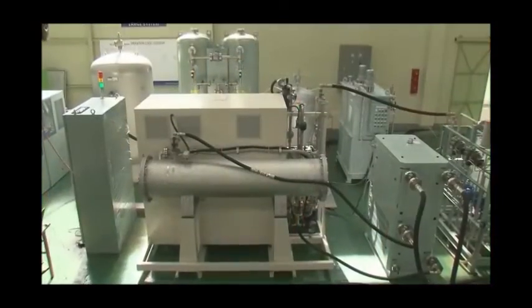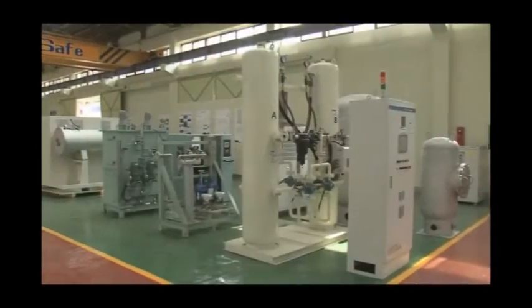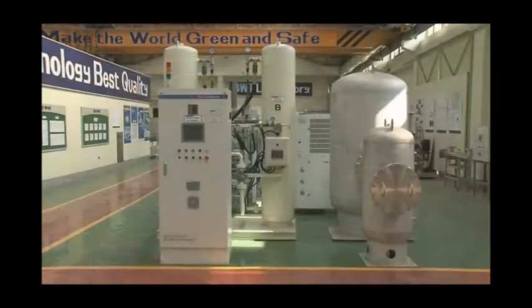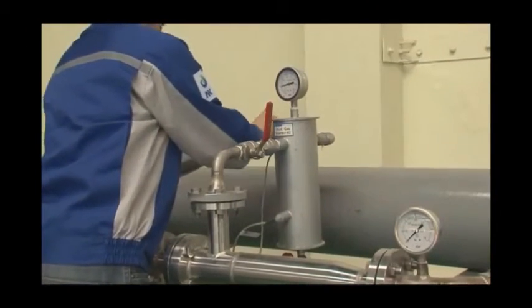NK03 blue ballast system is designed to inject ozone into the ballast water flow at rate less than 2.5 ppm during ballasting time. Therefore, the key part is to fit ozone injection unit at discharge side of ballast pump.